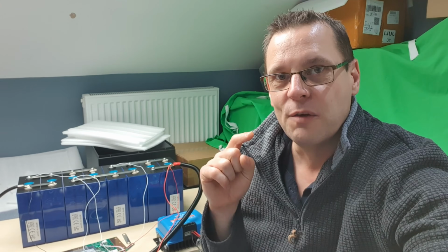Right, this is a little embarrassing. We've hit about 4 hours 45 minutes. Capacity was about 542 amp hours of total current draw. Now, as you would have seen earlier on when I showed you through the configuration, I set the cutoff voltage on the BMS to be slightly higher than that of the meter. So what actually happened is the BMS did its job: it hit low voltage cutoff, powered off the system and powered off the voltage meter, and it completely wiped out all of the details. So I've turned it all back on and everything's gone back to zero, which is really frustrating. But certainly we hit 542 amp hours at a cutoff of 2.8 volts.